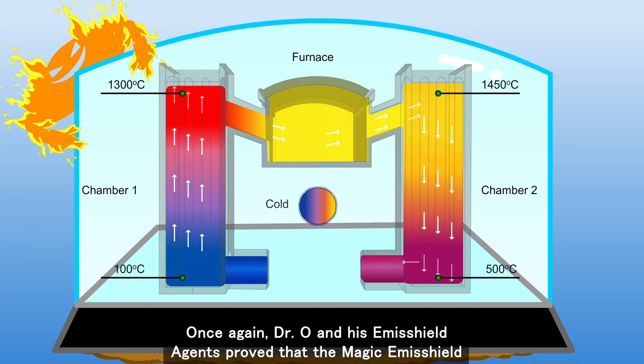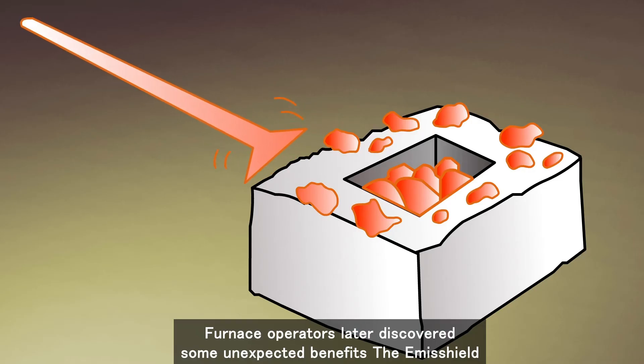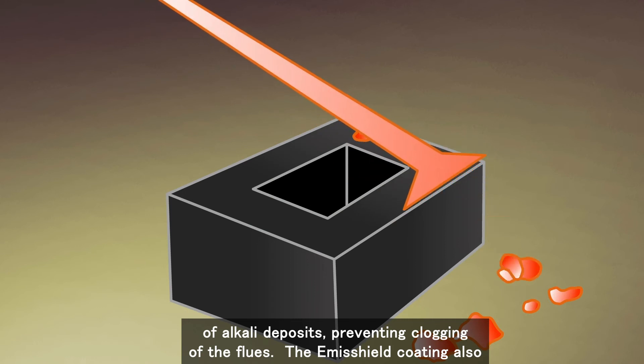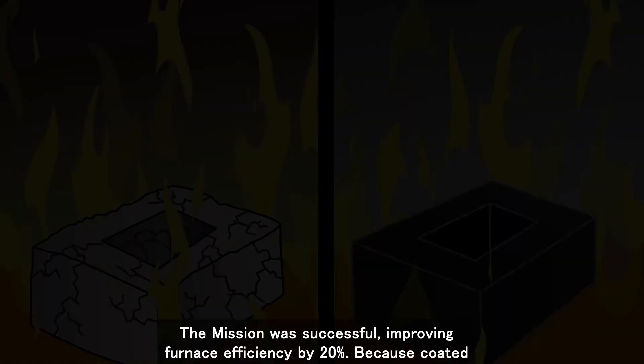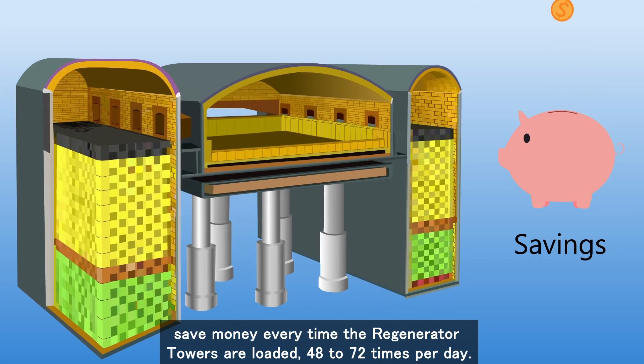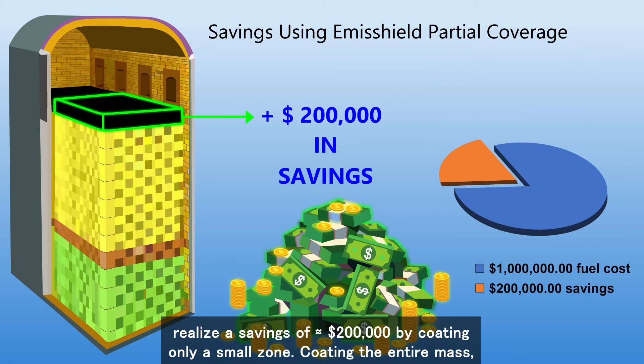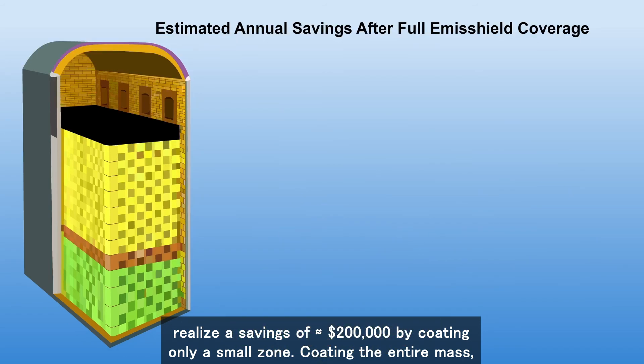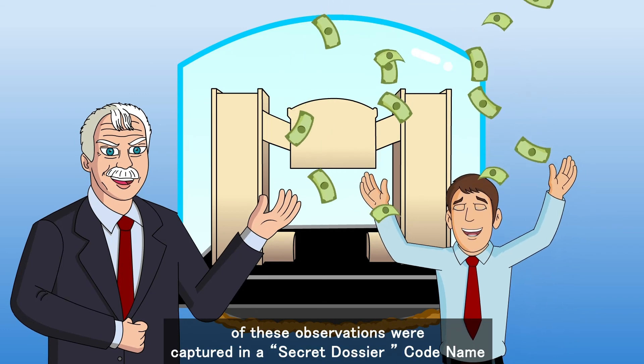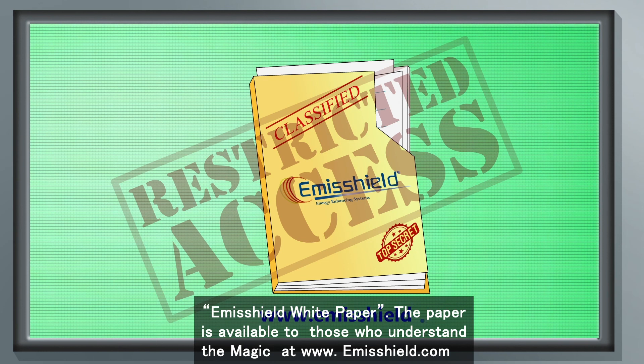Once again, Dr. O and his Emisshield agents proved that the magic Emisshield coating protected towers from heat-stealing demons and kept the regenerators from being swallowed by profit-destroying thermal money pits. Furnace operators later discovered unexpected benefits: the Emisshield-coated checker surfaces were less porous and more resistant to the adherence of alkali deposits, preventing clogging of the flues. The coating also improved resistance to thermal shock, further increasing lifespan. The mission improved furnace efficiency by 20%, saving money every time the regenerator towers are loaded 48 to 72 times per day. Assuming an annual energy cost of one million dollars, operators could realize savings of over $200,000 by coating only a small zone. Coating the entire mass and superstructure sidewalls could mean an even better ROI. The details of these observations are available in the Emisshield White Paper at www.emisshield.com.